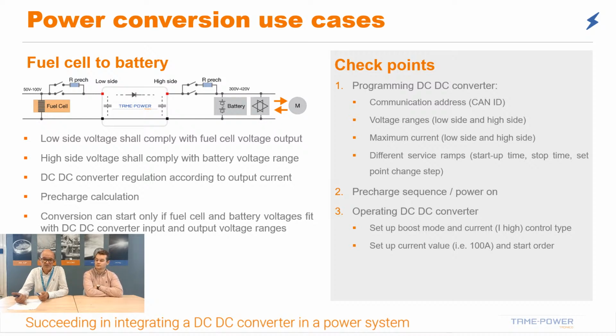You can check this situation because the DC-DC converter has internal voltage, current, and temperature measurement on the input, on the high side, and on the low side. So it means you can evaluate by yourself if the voltage conditions are correct before connecting anything.